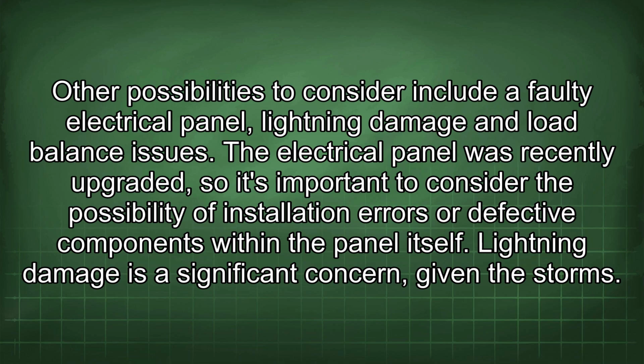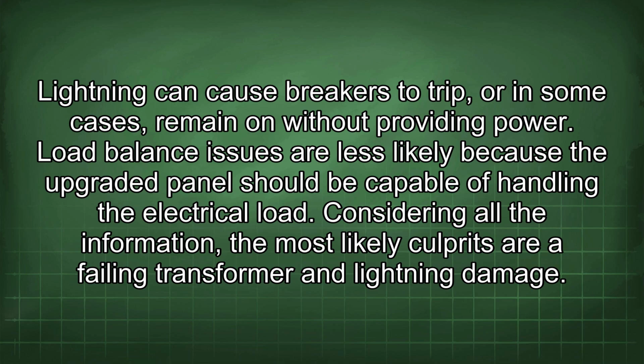The electrical panel was recently upgraded, so it's important to consider the possibility of installation errors or defective components within the panel itself. Lightning damage is a significant concern given the storms. Lightning can cause breakers to trip, or in some cases, remain on without providing power. Load balance issues are less likely because the upgraded panel should be capable of handling the electrical load.